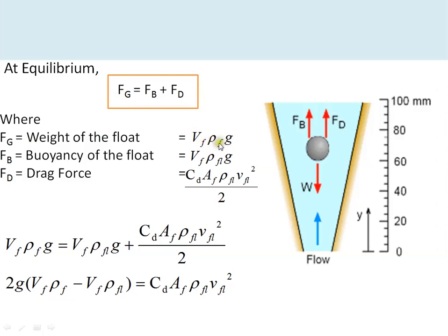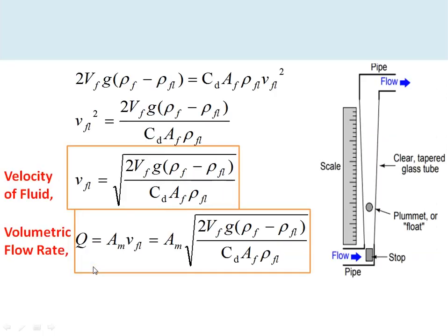The weight of the float equals its mass times g, where mass equals volume of the float (V_f) times density of the float (ρ_f). The buoyancy force equals V_f times the density of the displaced fluid times g. The drag force equals C_D times A_f times the fluid density times V_F² divided by 2, where C_D is the drag coefficient, A_f is the float area, and V_F is the fluid velocity. Solving the equilibrium equation gives V_F as the square root of [2·V_f·g·(ρ_float − ρ_fluid) / (C_D · A_f · ρ_fluid)]. The volumetric flow rate Q equals the tapered annular area at that position times V_F.